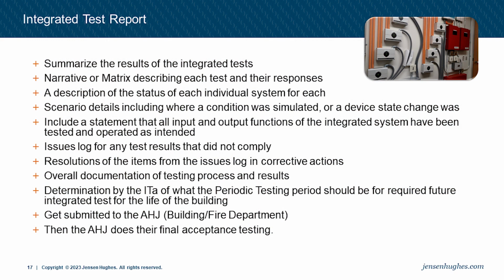So, the integrated testing report. Yes, there is a report that gets pulled together and handed over to the building officials. It includes all that information and the results of the integrated test: a narrative or matrix describing each test and its responses, a description of the status of each individual system, and scenario details including where a condition was simulated or a device state changed. You need to include a statement that all inputs and output functions of the integrated systems have been tested and operate as intended. You do need to have an issues log for any test results that did not comply, and then a resolutions log for those items that were corrected.